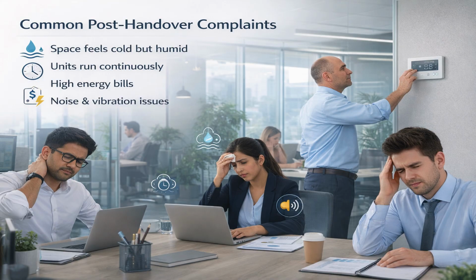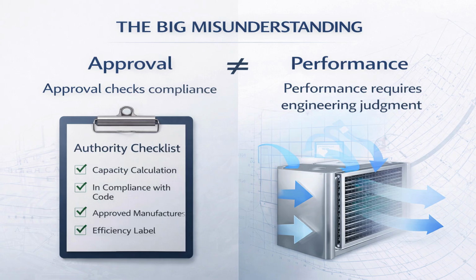And this gap between what looks right in the documents and what actually happens on site is where the real engineering begins. Because at that point, we are no longer dealing with approvals or paperwork. We are dealing with performance. And performance always exposes what was missed earlier. Authority approval plays an important role in our projects. It confirms that the design meets minimum code, standards, and regulations. But approval alone does not tell us how the system will actually behave once the building is occupied. It does not verify how the unit will respond to real heat gains, real humidity levels, part load operation, or the way occupants actually use the space.